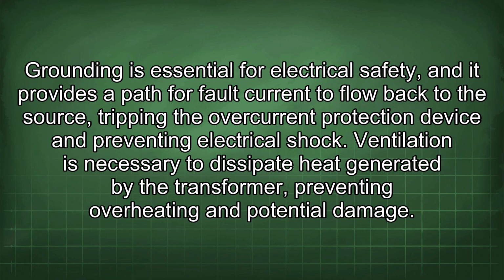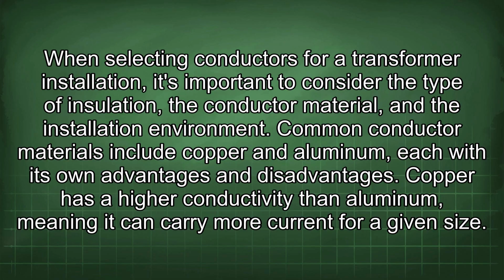Grounding is essential for electrical safety, and it provides a path for fault current to flow back to the source, tripping the overcurrent protection device and preventing electrical shock. Ventilation is necessary to dissipate heat generated by the transformer, preventing overheating and potential damage. When selecting conductors for a transformer installation, it's important to consider the type of insulation, the conductor material, and the installation environment. Common conductor materials include copper and aluminum, each with its own advantages and disadvantages. Copper has a higher conductivity than aluminum, meaning it can carry more current for a given size.